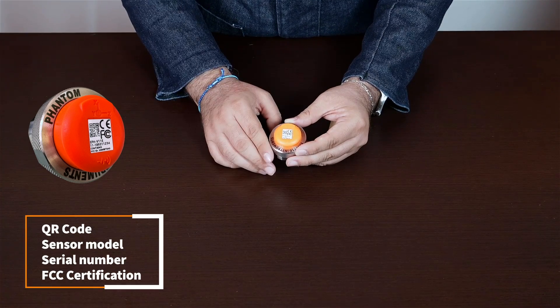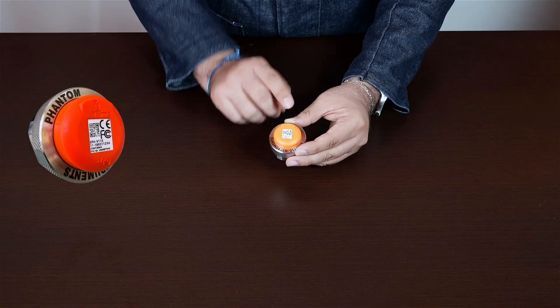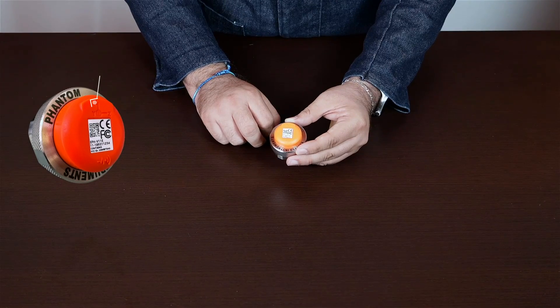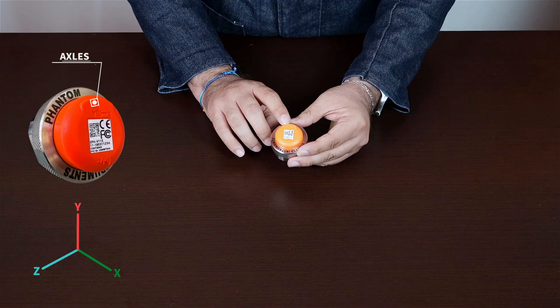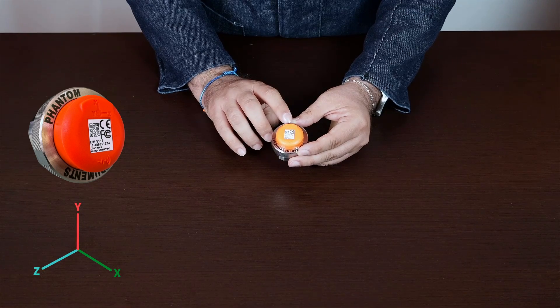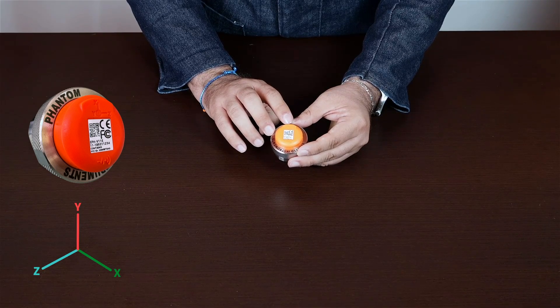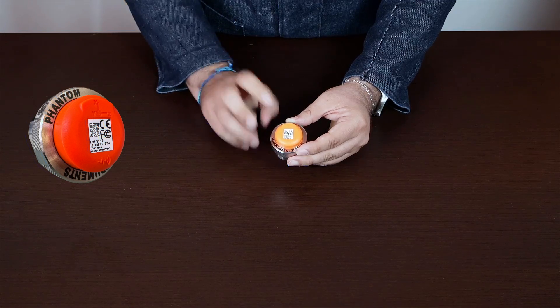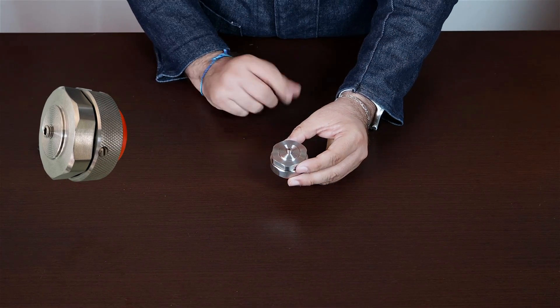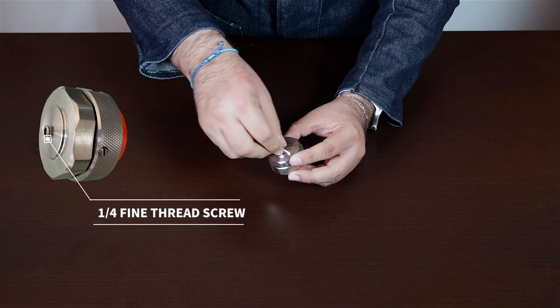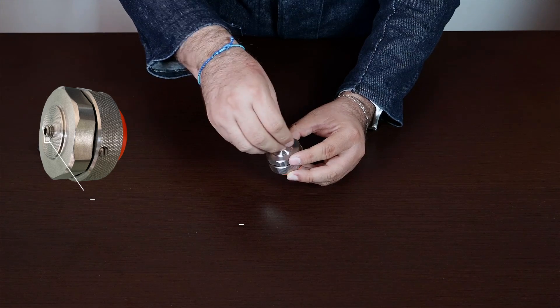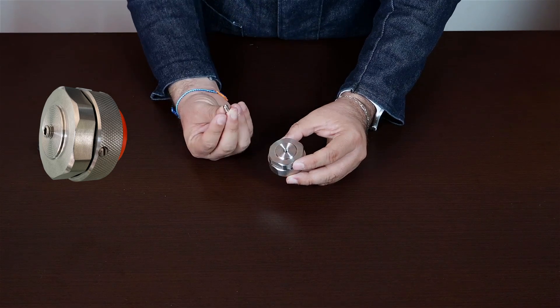Additionally, you can find its axes engraved at the top. These axes not only represent the brand but also indicate the direction the accelerometers are pointing to. It's important that when you place them on your machines, these axes are pointing to your desired directions. At the bottom, you will find the sensor base with a fine thread set screw. This set screw can be removed for independent operation, giving us multiple mounting options.